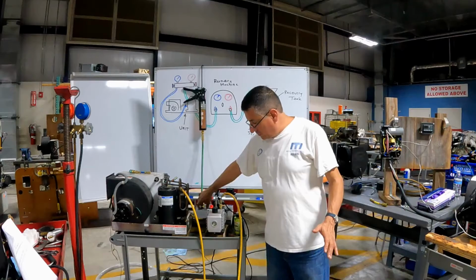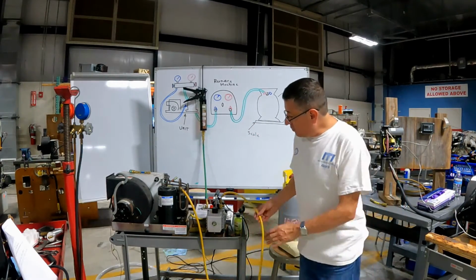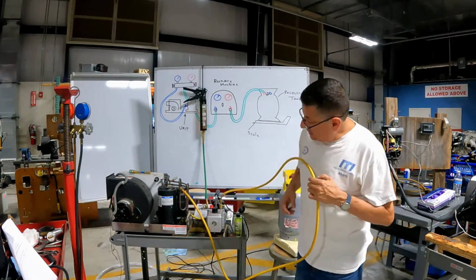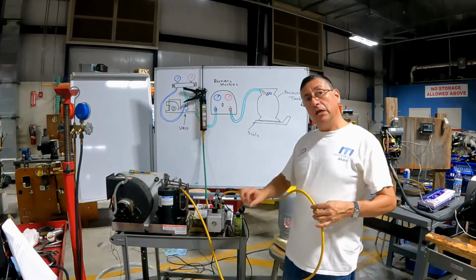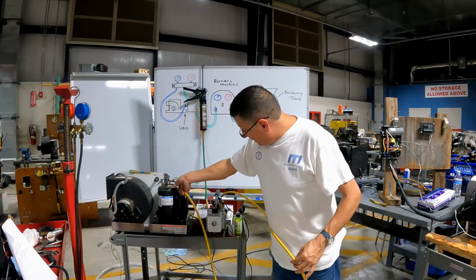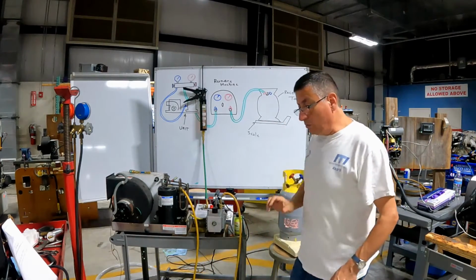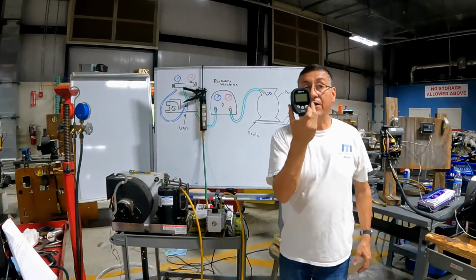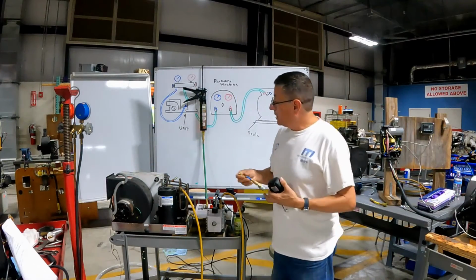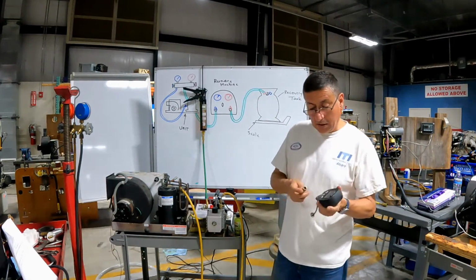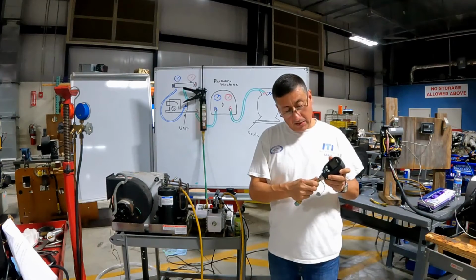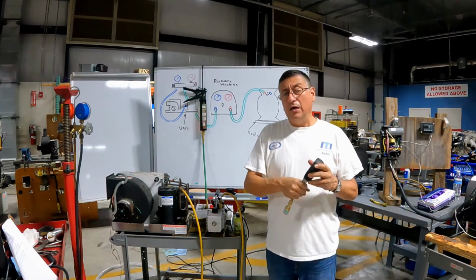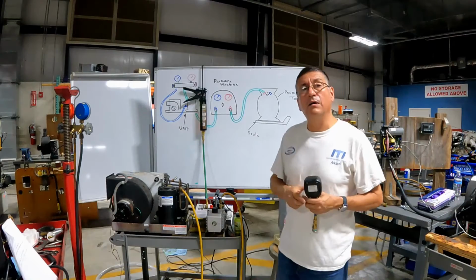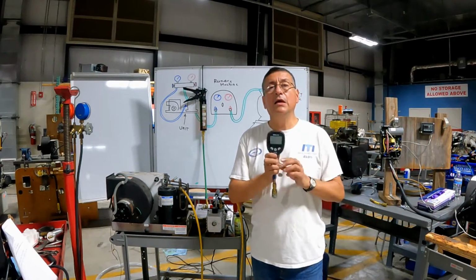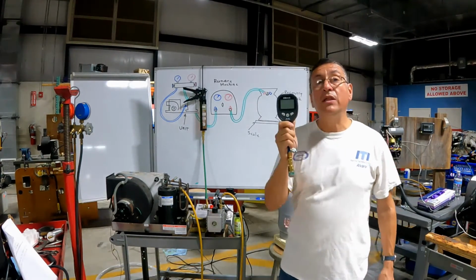Okay, we are going to do the vacuum process. We are going to connect our vacuum pump. This is the valve. We verify that the level of oil is appropriate. We connect it to the equipment, and after that we get ready with the vacuum gauge. I connect the fitting here, the adapter, in order to connect the vacuum gauge properly. And we are going to apply power on the pump until the reading on the vacuum gauge is around 500 microns.